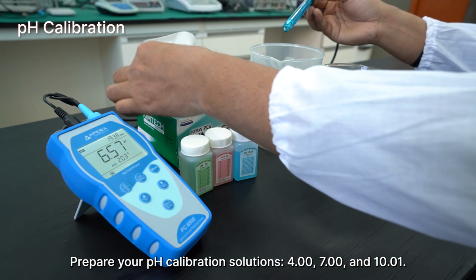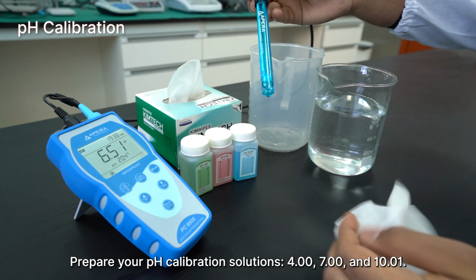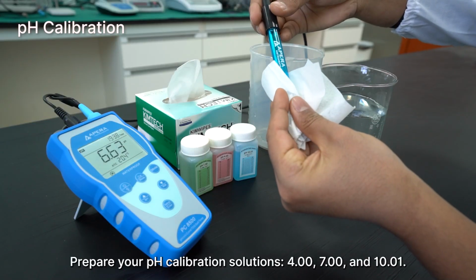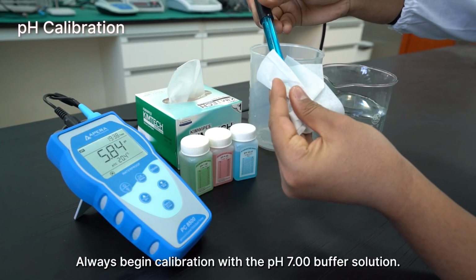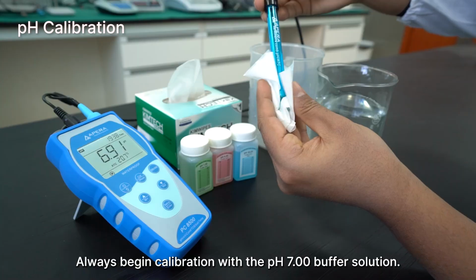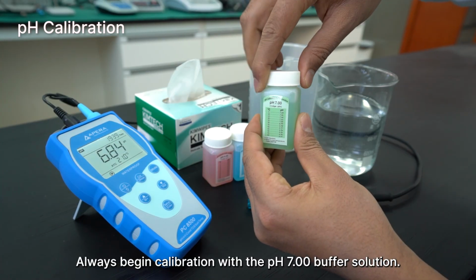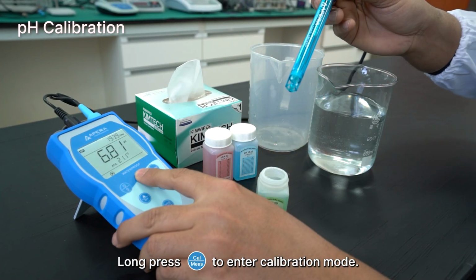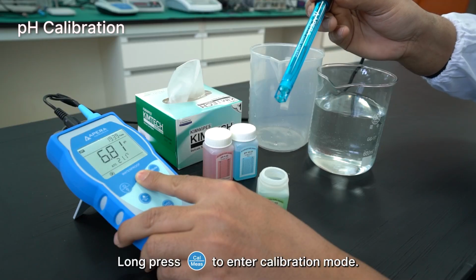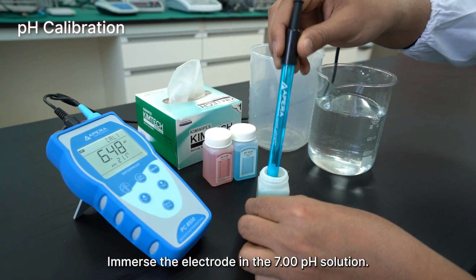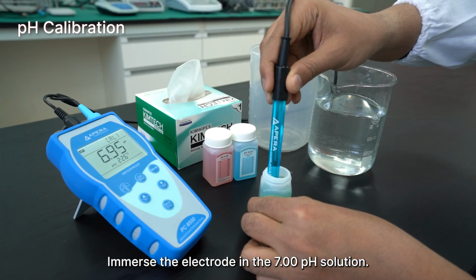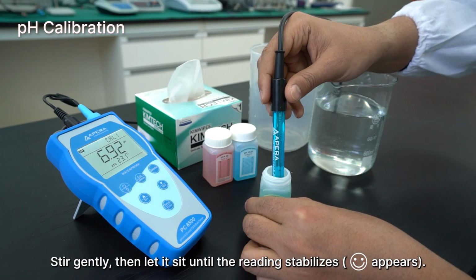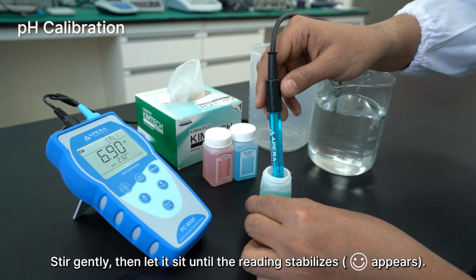Prepare your pH calibration solutions, 4.00, 7.00, and 10.01. Always begin calibration with the pH 7.00 buffer solution. Long press the cal button to enter calibration mode. Immerse the electrode in the 7.00 pH solution. Stir gently, then let it sit until the reading stabilizes.